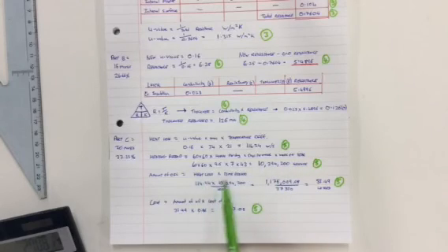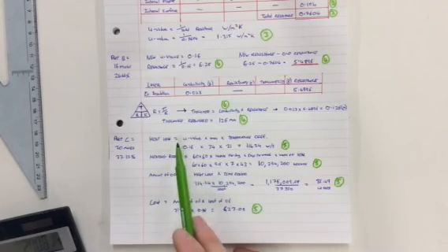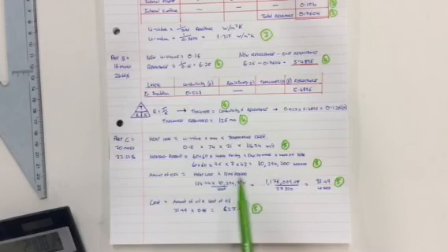Here's where it gets a little bit more tricky. The amount of oil is the heat loss multiplied by the time period. That's the heat loss from the first part, and the time period is what you've done in the second part, and dividing it by 1,000. Then your answer is divided by 37,350, the calorific value of the oil. That's the total energy required, and that's the energy that 1 litre gives out.